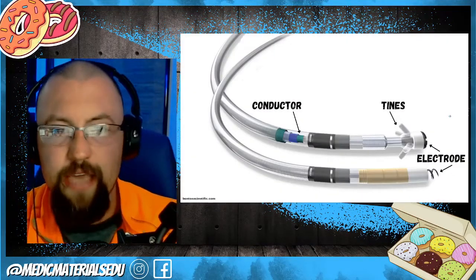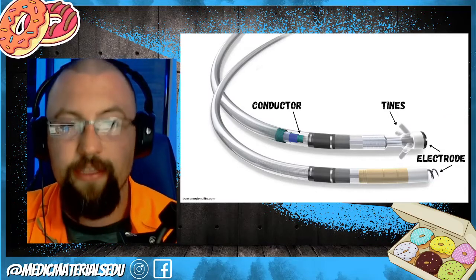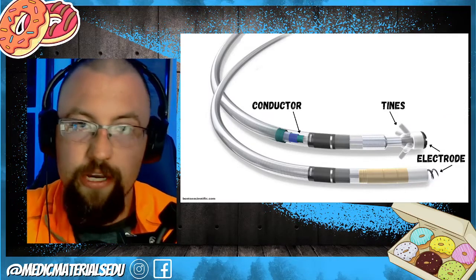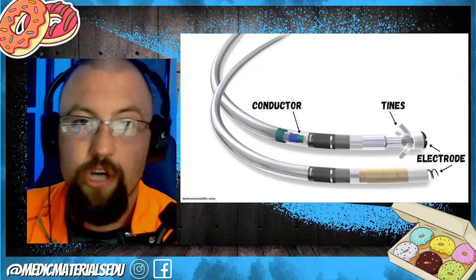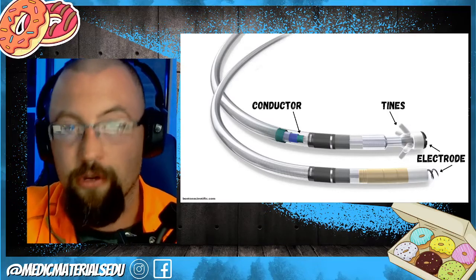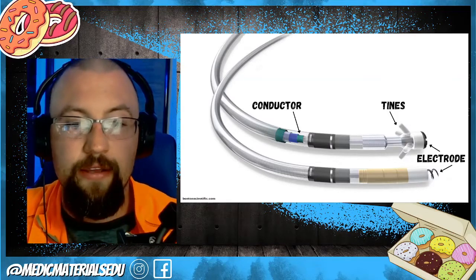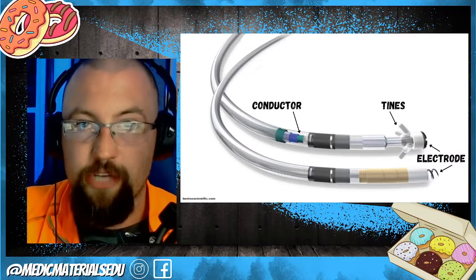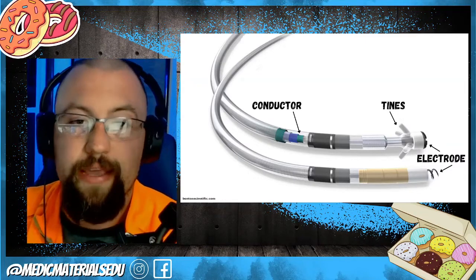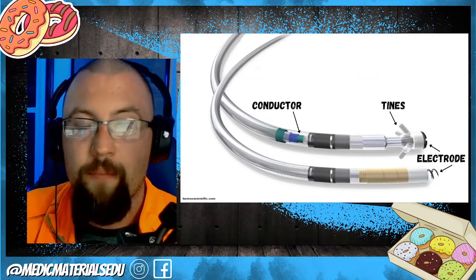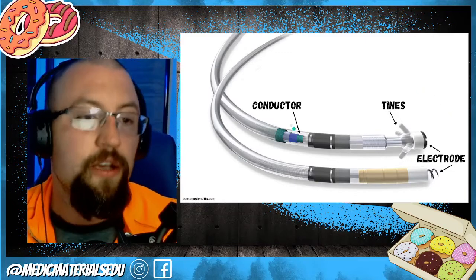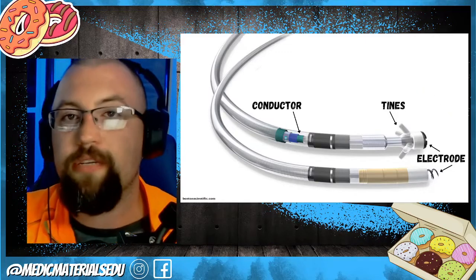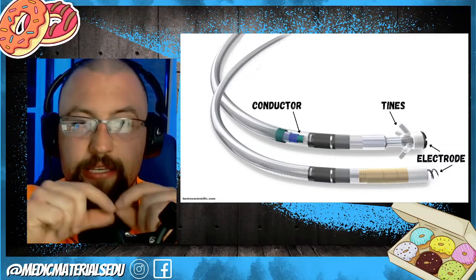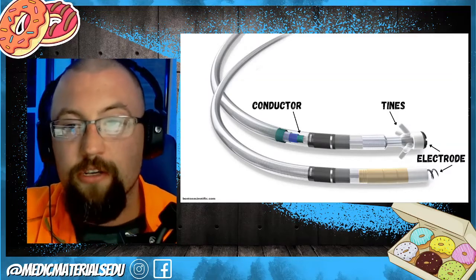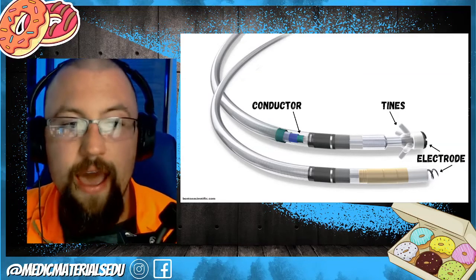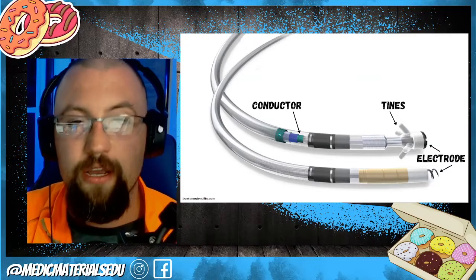Then you actually have the leads. Okay. Now the leads conduct that electrical charge from the pulse generator. They connect directly to the pulse generator, and then they are secured into the myocardium muscle themselves. So one of the things that they found out through testing was that they stopped using conductor wire that was straight, and they went to this coiled conductor wire.